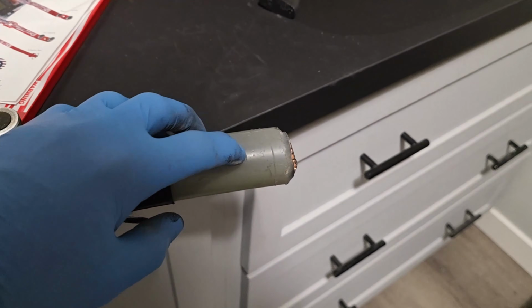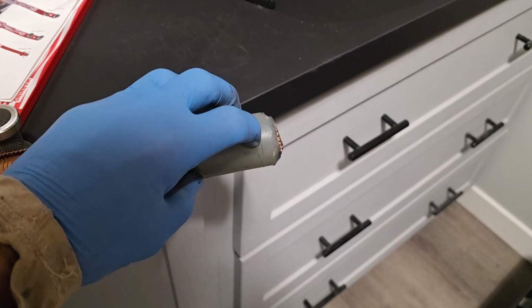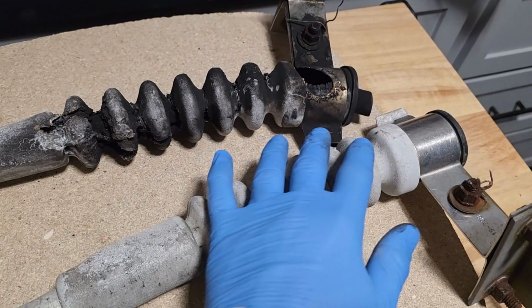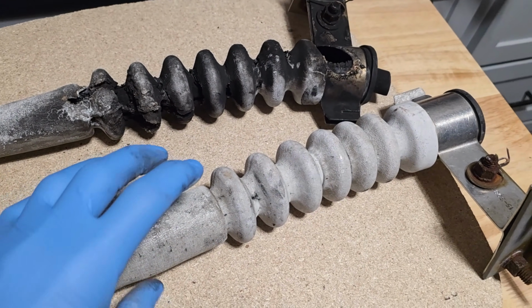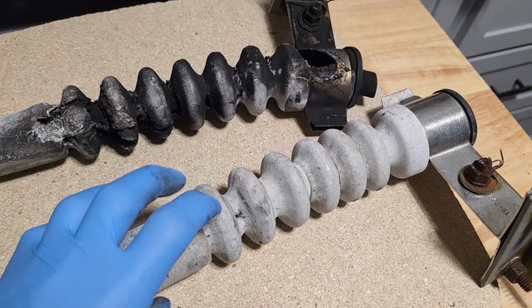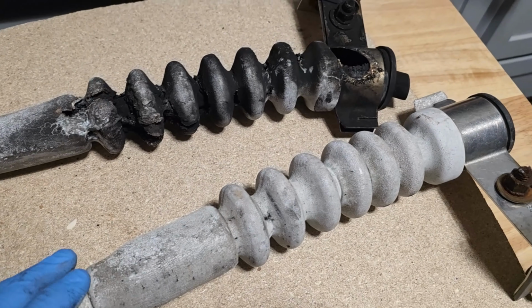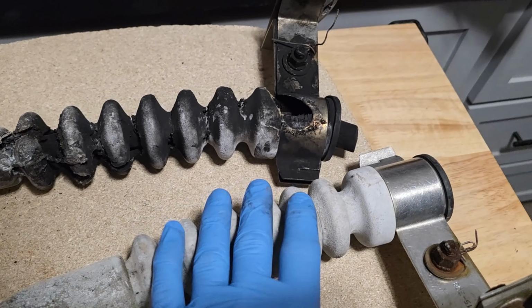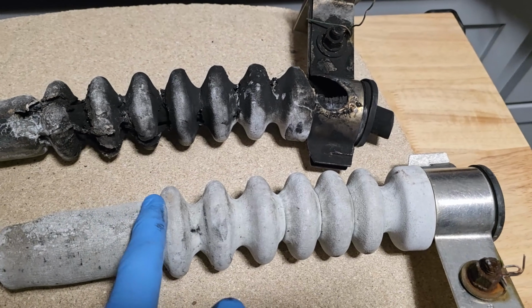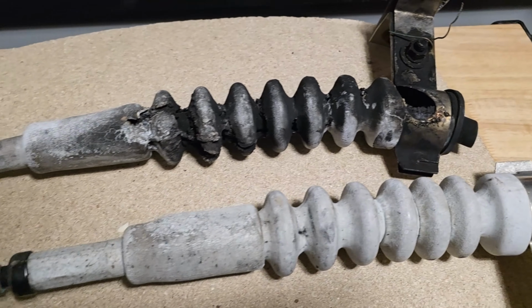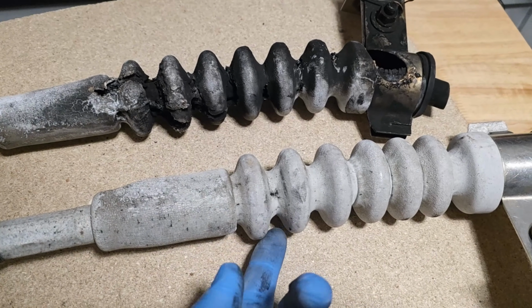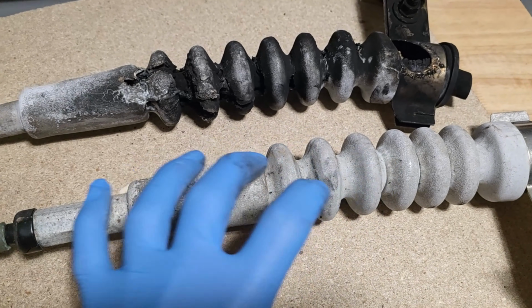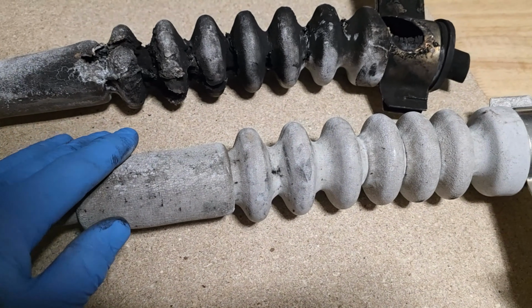Basically, the inside of that cable is 100% clean all the time. The insulation value maintains its value, whereas the outer layer of insulation breaks down, and it gets mineral deposits as the rainwater evaporates off. It becomes kind of conductive. The greater the surface area, the more of a distance. So as that electricity, where it's not going to come from the inside out because that insulation's in such good shape, it wants to travel on the outside.